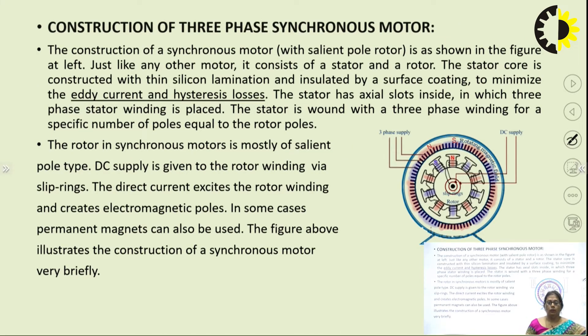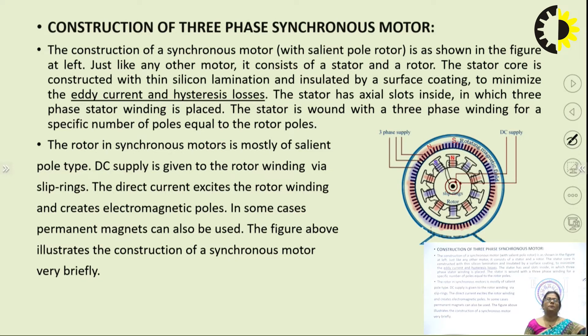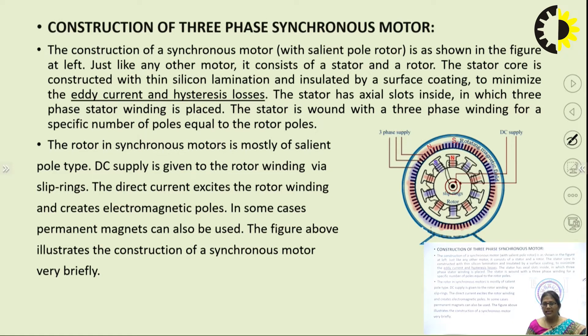Now coming to the motor construction. The three-phase synchronous motor stator is constructed of thin silicon laminations insulated by a surface coating to minimize eddy current and hysteresis losses. The stator has axial slots in which the three-phase stator windings are placed, generally in star connection. The rotor construction for a synchronous motor is generally the salient pole type, where poles project outwards.